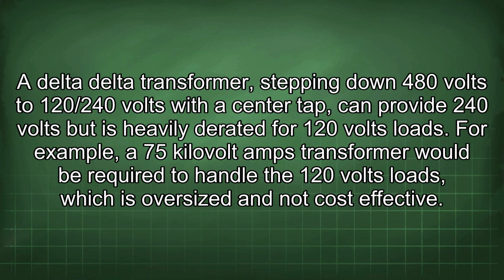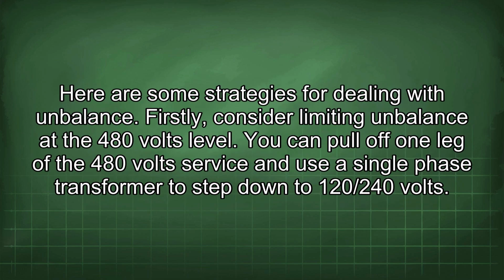A delta-delta transformer, stepping down 480 volts to 120/240 volts with a center tap, can provide 240 volts but is heavily derated for 120 volt loads. For example, a 75 kVA transformer would be required to handle the 120 volt loads, which is oversized and not cost-effective. Here are some strategies for dealing with imbalance.